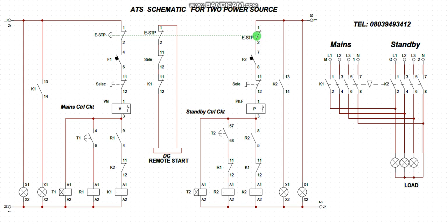So this is my emergency push button. This is also an emergency push button. And this emergency push button cuts across this other main supply and the start signal, and also this particular standby logic. So once you activate this emergency push button, 1, 2, 3 will be disabled. So you cannot start the gen, and the power cannot go in. The generator cannot start, and the mains cannot go in, like the function of this.